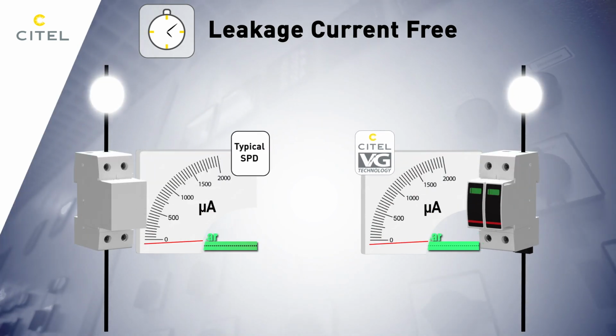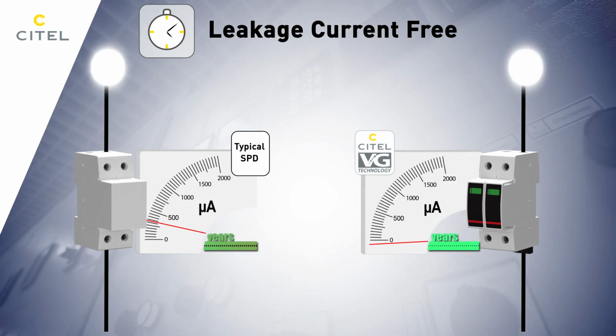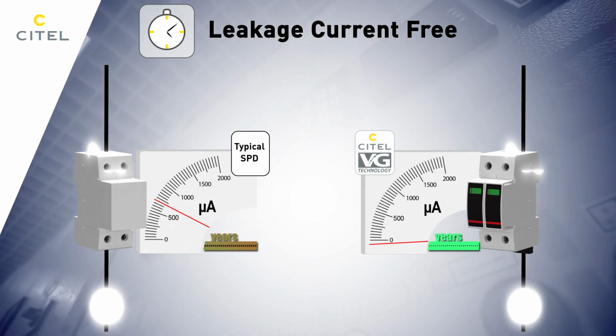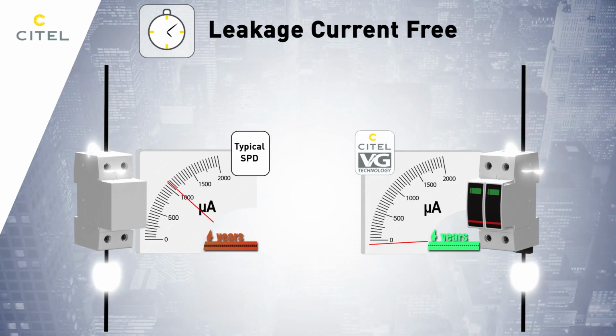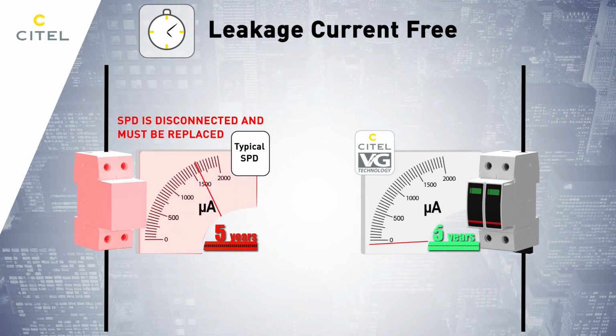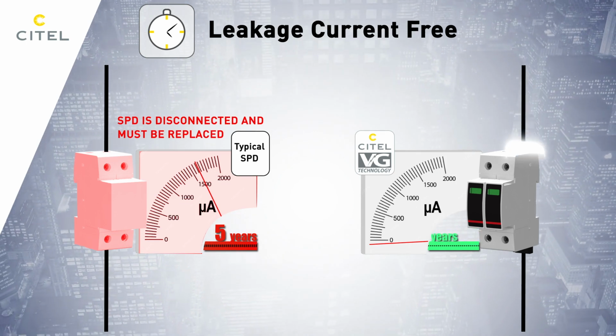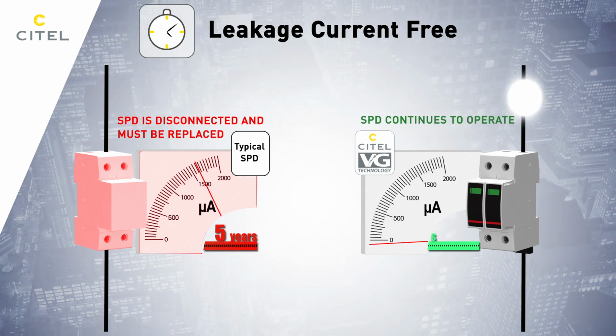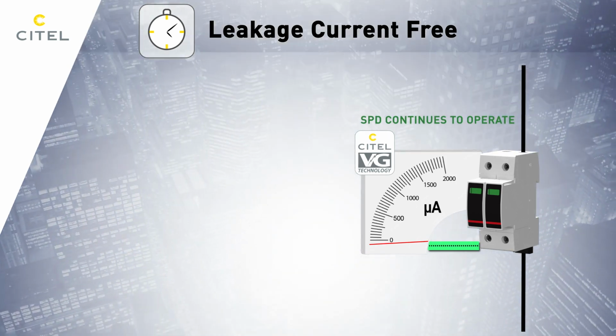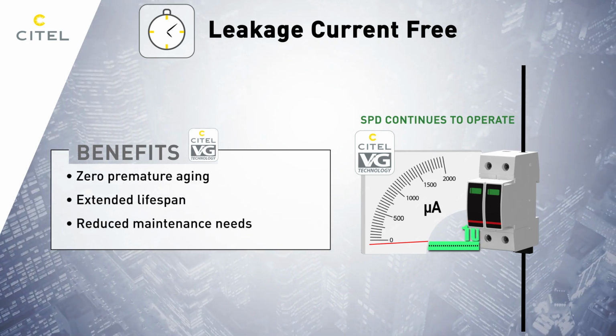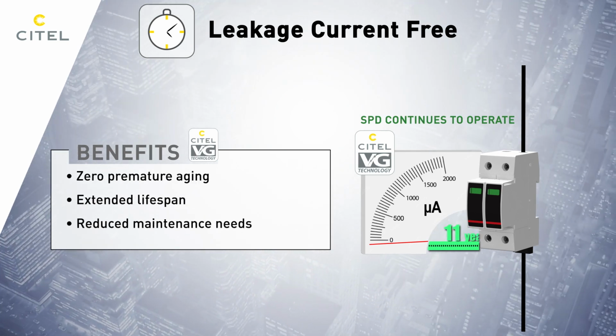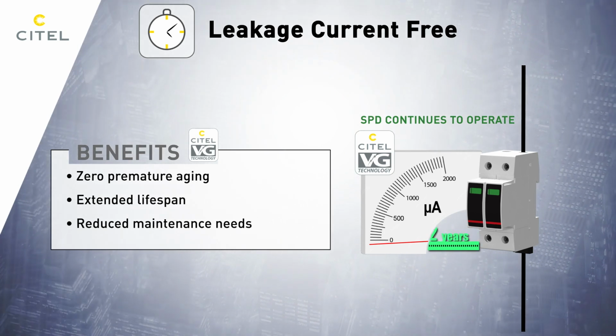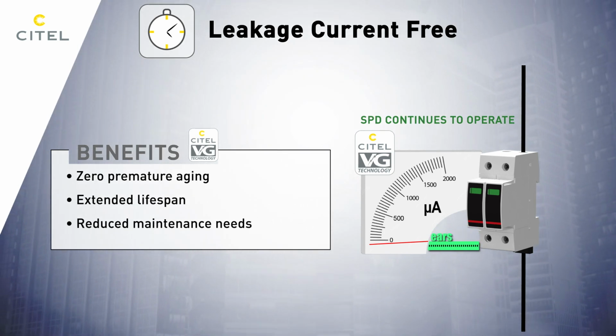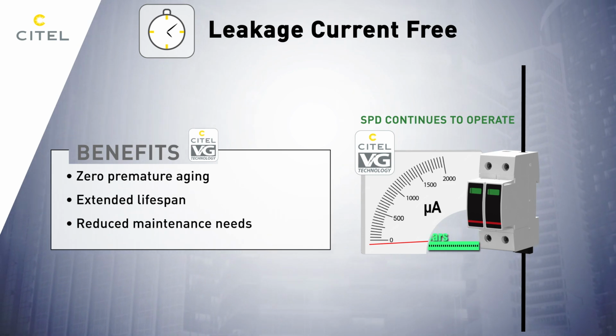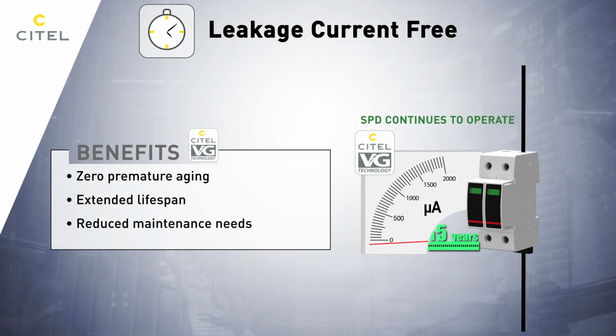Most surge protection devices draw a small continuous current even when no surge is present. This occurs due to the internal components of the SPD, such as MOVs, which can create a minor conductive path in normal operation. This leakage current, though minimal, can generate unwanted heat, accelerate component aging, and reduce energy efficiency. With VG technology, the SPD does not draw any current during normal operation, resulting in zero power consumption, zero premature aging, and most importantly, extended lifespan for the entire system, reduced maintenance needs, and reduced overall environmental impact of electrical systems.